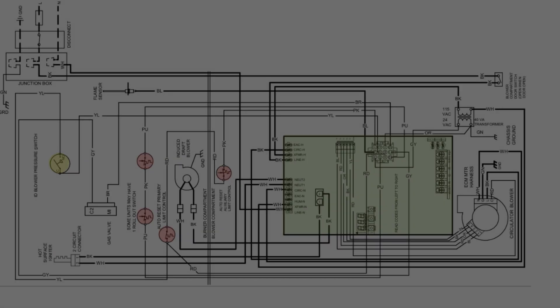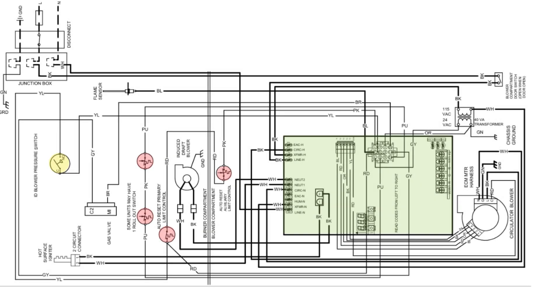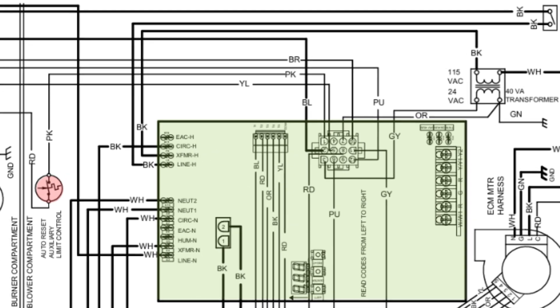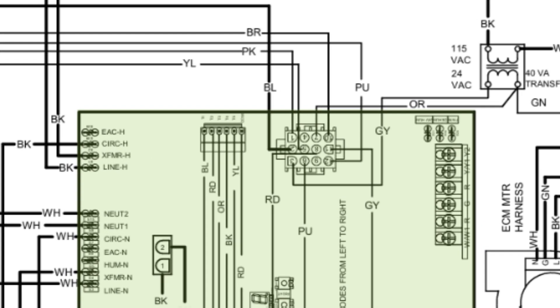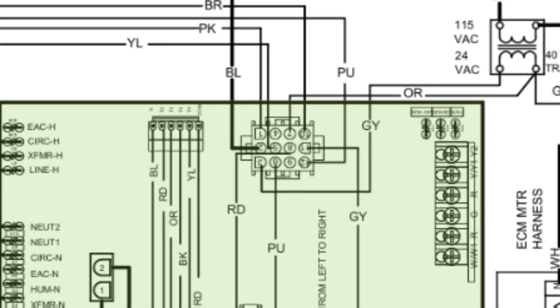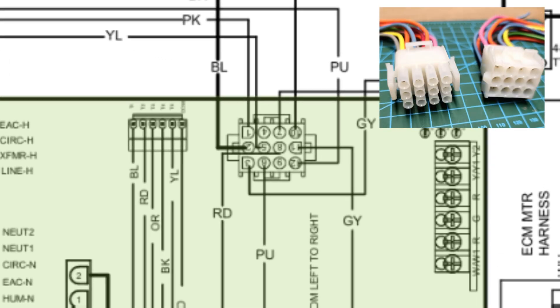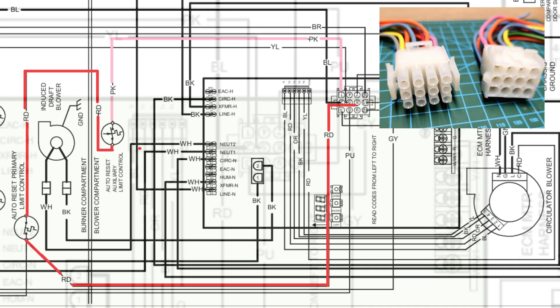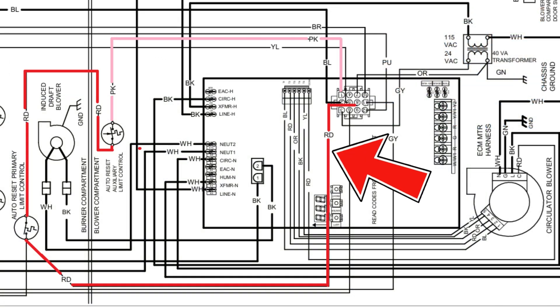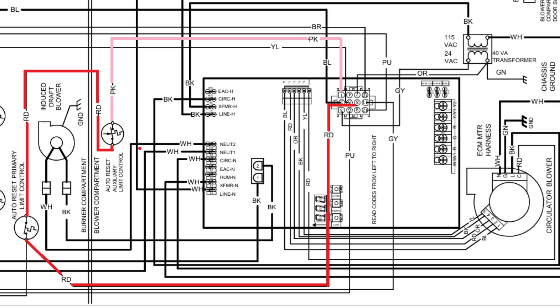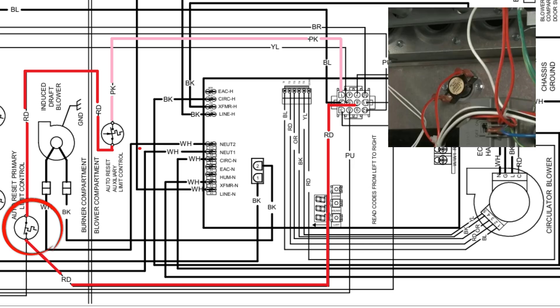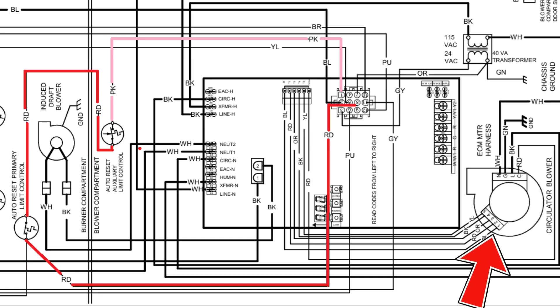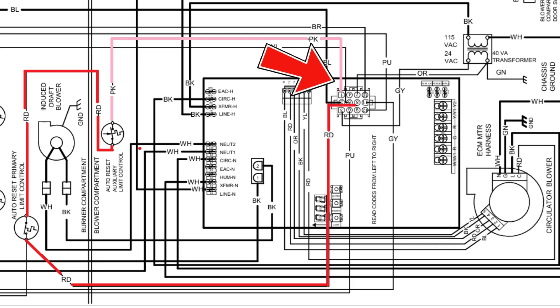So let me pull up this schematic. It's for a furnace, and if you look at the control board on here, you'll see a Molex plug with a whole bunch of wires coming off of it. Now, if you ever trace these out, you might see, for example, a red wire coming off the Molex plug. It goes through your high limit switch by the heat exchanger, maybe goes through another high limit that's located on the blower casing, or maybe it's on the furnace exhaust, the flue pipe, and then comes back to the Molex plug on, in this case, a pink wire.